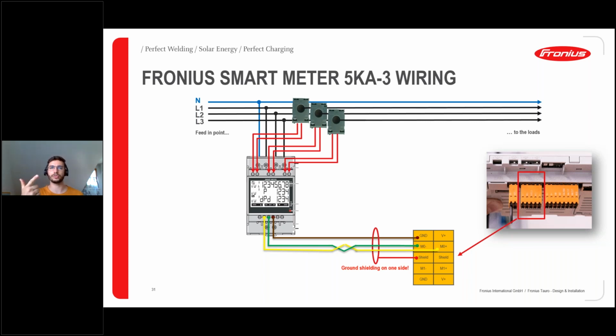The second very important topic is to ground the shield on one side. A Cat5 cable or a higher standard does have a shield on the cable, and we need to make sure to ground it on one side, which is no problem on the Tauro side, because we also have one prepared here, a separate plug, a pin which is already called shield. And this is meant exactly for that, to ground the shield on one side here. This is topic number 2.